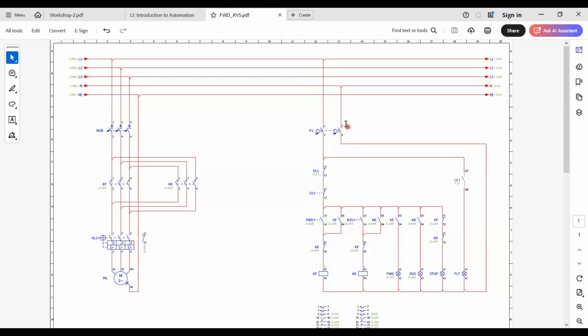Again, for the protection of the control circuit, we need to use a circuit breaker or a fuse. But here we have used a two-pole circuit breaker. Depending on the current rating of the system, you have to select it. Then it goes to the line, and this is the neutral. So the neutral is common to all the contactors and light indicators. Now let's see, this is the current from one phase going to the overload. If there isn't any overload event, if the motor is running in normal conditions, this normally closed contact is closed. So it allows the current to flow through here.